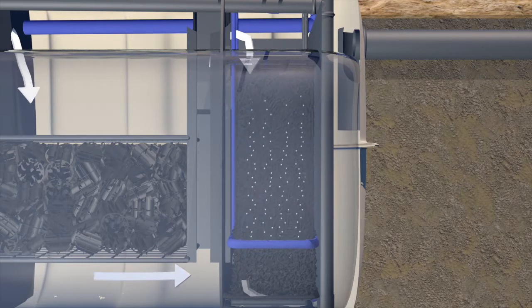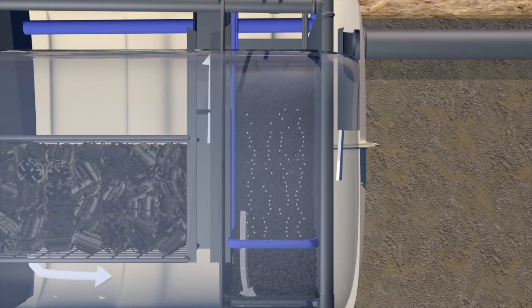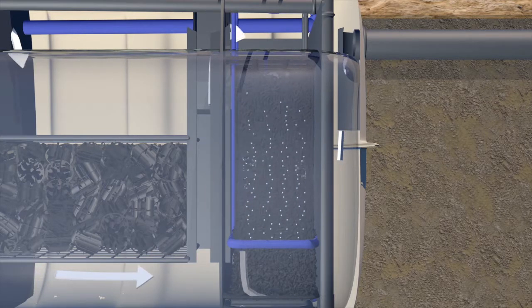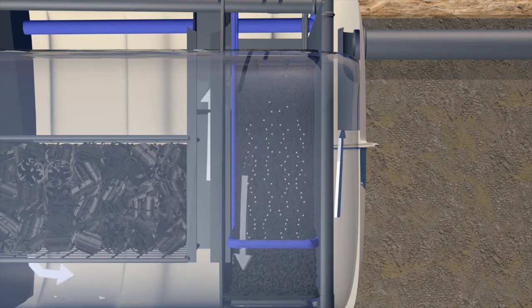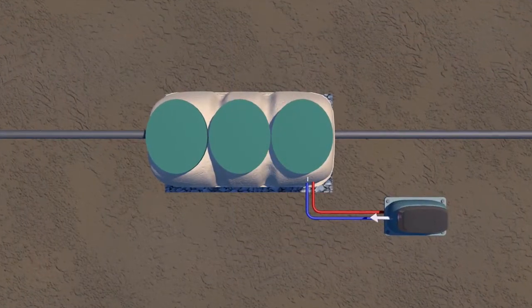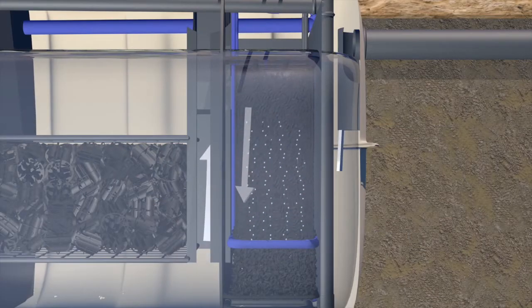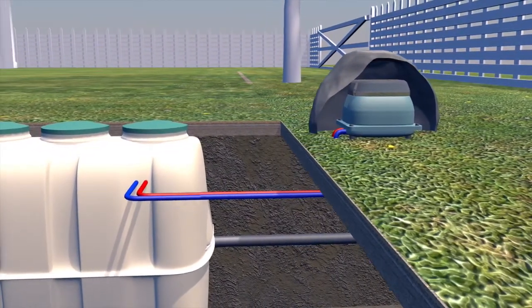This fluidized bed is filled with specially designed media on which aerobic bacteria can grow. This chamber has two separate air piping grids. The upper grid is activated nearly all the time, providing air to aerate and tumble the upper 2/3 of the media while allowing the remaining 1/3 to serve as a mechanical filter. The Fusion's dual outlet blower provides air to oxygenate this compartment, and it powers the aeration, recirculation, and backwash operations. The low energy consumption blower makes the Fusion very economical to operate.